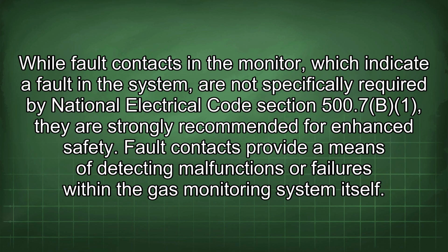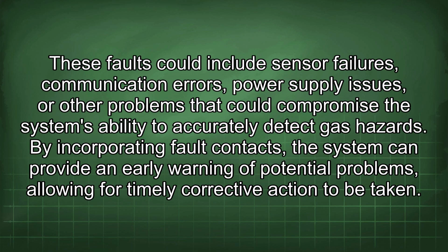While fault contacts in the monitor, which indicate a fault in the system, are not specifically required by National Electrical Code Section 500.7(B)(1), they are strongly recommended for enhanced safety. Fault contacts provide a means of detecting malfunctions or failures within the gas monitoring system itself. These faults could include sensor failures, communication errors, power supply issues, or other problems that could compromise the system's ability to accurately detect gas hazards.